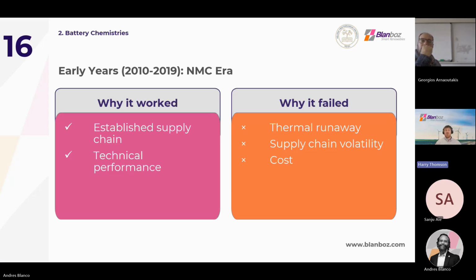These days there are still legacy projects using NMC batteries, but we aren't seeing any more being built, and haven't for the last few years since the takeoff of LFP. One reason for this is thermal stability concerns. NMC can begin self-heating at approximately 100 degrees Celsius, and once it reaches thermal runaway at around 170 degrees Celsius, it continues to release oxygen, feeding the thermal event and accelerating it further. This all leads to NMC having a more energetic thermal propagation than other technologies, which is a huge safety concern.